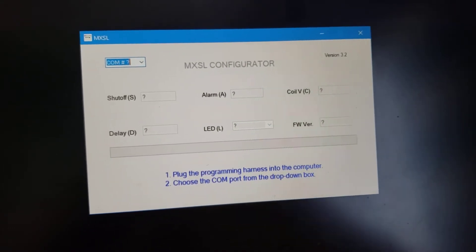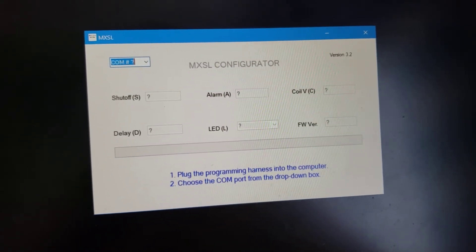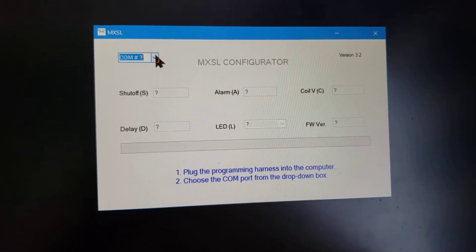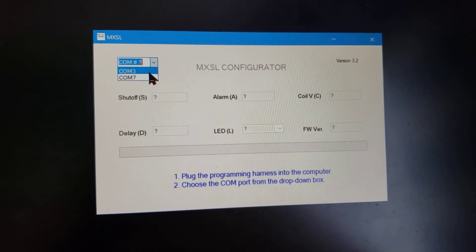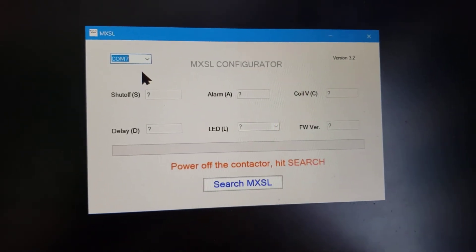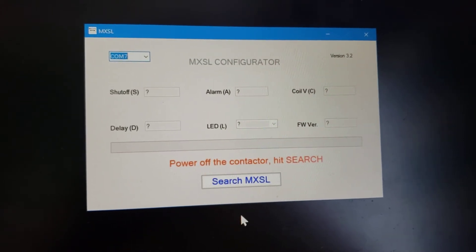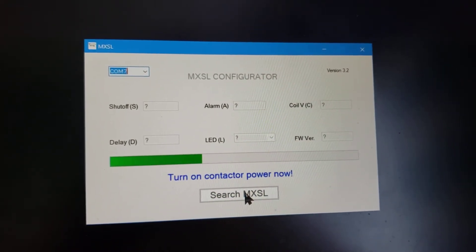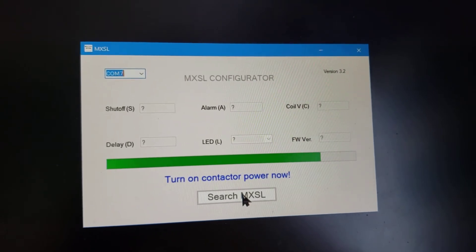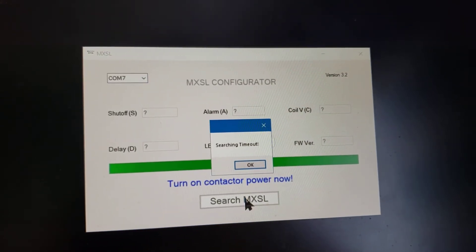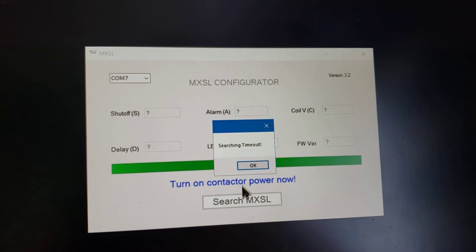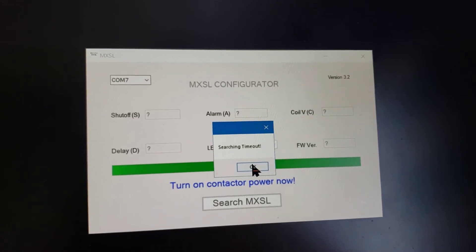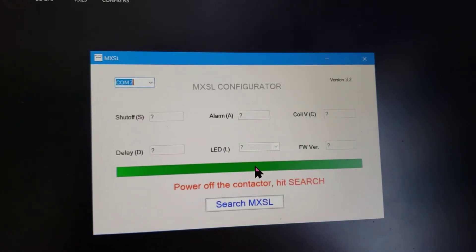So the first step is you must select which COM port you're connected to. In my case, I believe that is COM port number seven. So I'm going to select that. Now, if I click for search MXSL, it's going to try to connect to it and you'll see the green status bar go across the page. That's how much time you have to turn the power on. If you don't turn the power on, your session's going to time out and you'll get a little pop-up just like this. So let's close that pop-up.